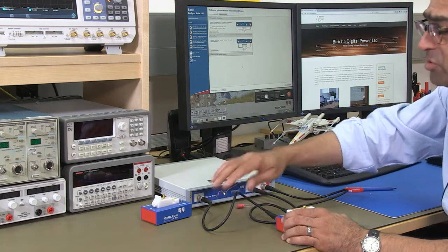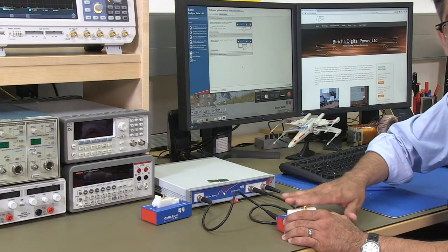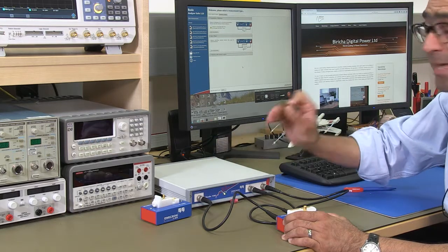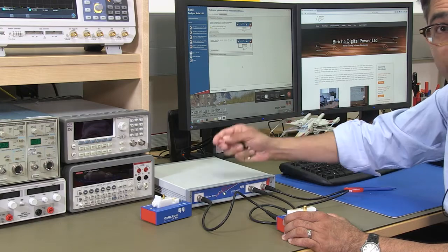However, we need to cancel out the impact of these cables and the actual test fixture itself, and therefore it is very important to calibrate the device. We do that with a calibration test fixture first, before we do the measurement, and that will improve our accuracy.